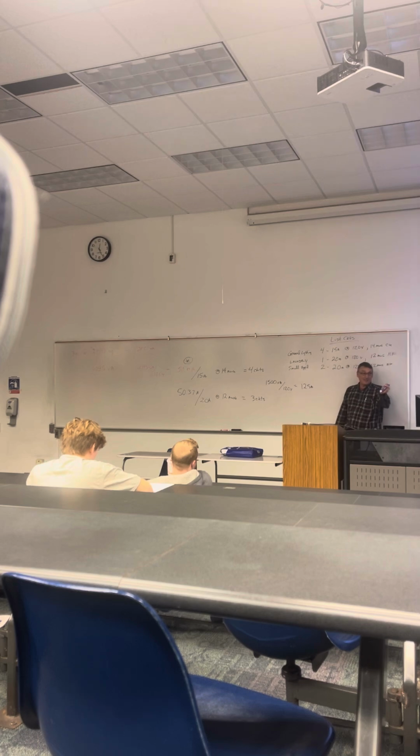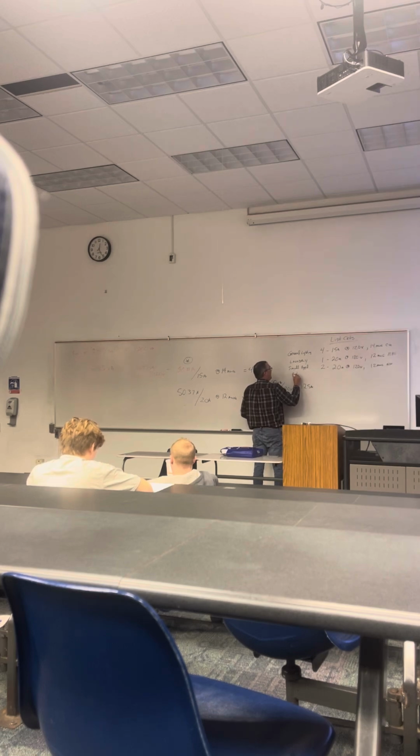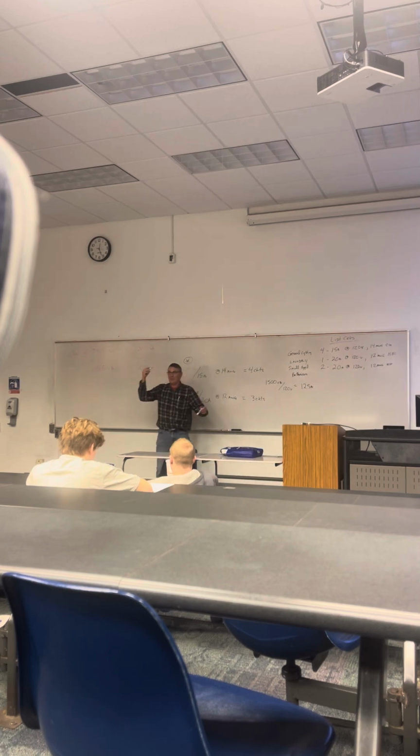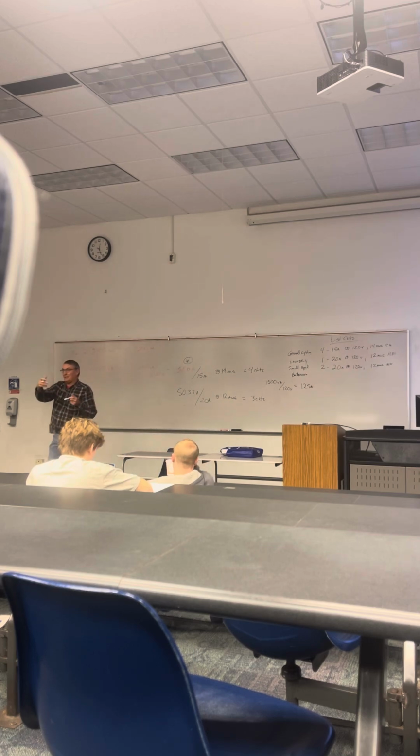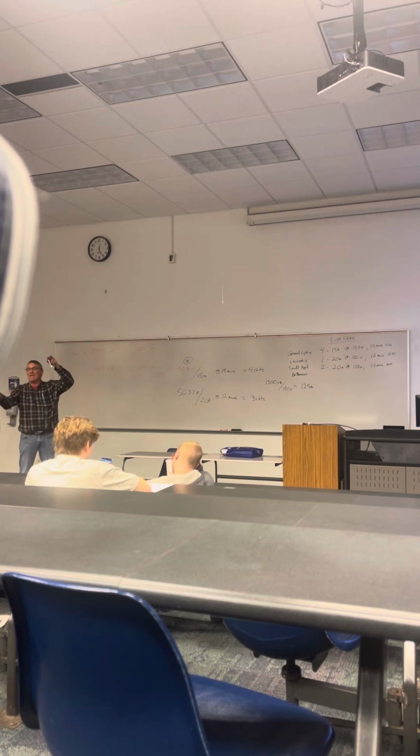And on the list, how many bathrooms were there? 2. 2 bathrooms, right? It doesn't go towards calculations, but you've got to provide them in the panel. They don't go towards the VA calculation, so you've got to have bathroom circuits. And how you wire them, you can't wire both bathrooms on the same circuit if you hook lights to it. You can't run the bathroom fan on the same circuit if you feed both of them on one circuit. There's a whole list of things that you can and can't do.